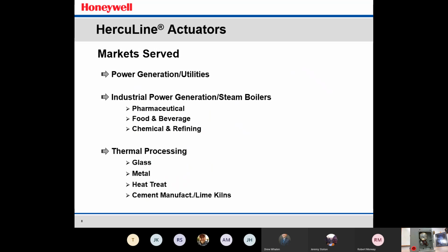We discussed some of the markets served. Again, power gen, utilities, pharmaceutical, food and beverage, chemical. These are used on a lot of large utility boilers inside of these facilities, on the ID fan dampers, also the gas valves. In the thermal processing market, you'll see these a lot in glass, metal, heat treat, cement manufacturers, lime kilns, really harsh environments where the actuators need to have a good hard casing on the outside of it. A lot of times NEMA 4X, IP66 rated. So these things withstand a lot of harsh environments and are very ruggedized.